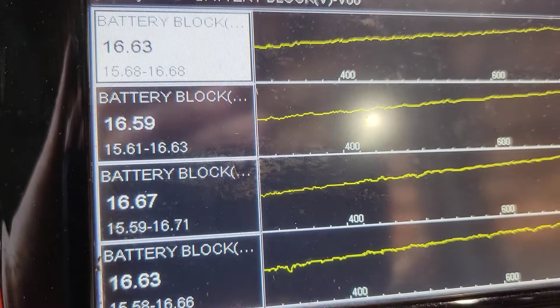So this is a dormant battery. It's not going to show me the failing right now because at this moment it's not failing, but it was failing earlier. So all the battery blocks should be within 0.5 volts of each other. If any of the blocks are outside that half a volt difference, then your battery is bad.